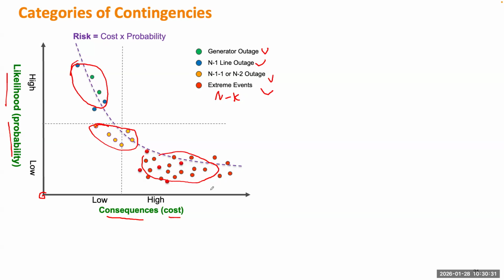So you can see all the contingencies stay along this hyperbolic curve. There are reasons for that, because if you multiply the cost by the probability, you can come up with an index, which you can call the risk. So all the contingencies will have about the same risk level. All right. But you may wonder why all the contingencies stay along this curve but not there, because if there's another curve, this one will have much higher risk. So the planning engineers, when they design or upgrade the system, need to make sure they push this curve as close to the X and Y axes as possible, right? If you have another system with a curve like this, the system is poorly designed.